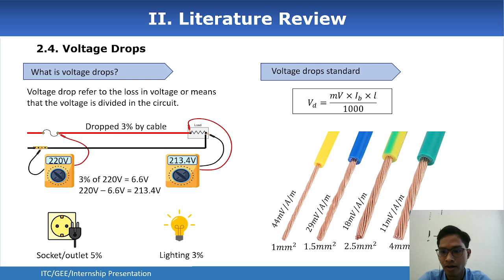For calculating the voltage drop, we use the formula Vd equals mV times Ib times L, divided by 1000. It means that the voltage drop depends on the current and the length of the cable. This picture shows the voltage drop for single core cable. For example, a 1 square millimeter single core cable has 44 millivolts per amp per meter voltage drop, and also for 1.5 square millimeter and so on. That means that when the cross-sectional area of the single core cable is bigger, the voltage drop is lower because the resistance in the cable is lower.